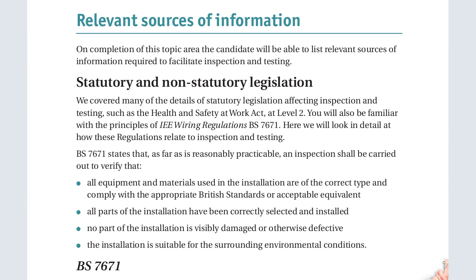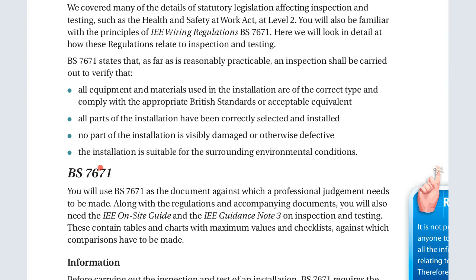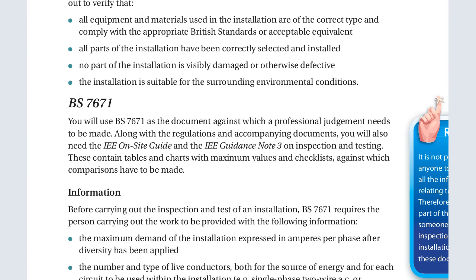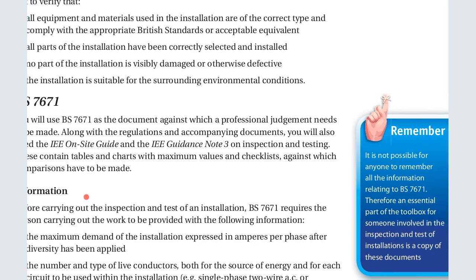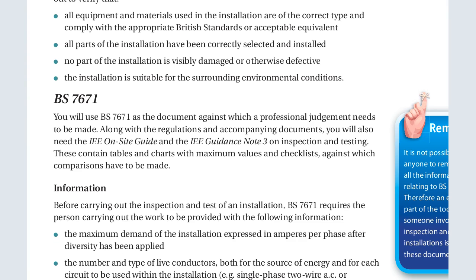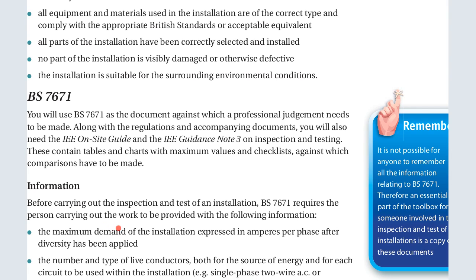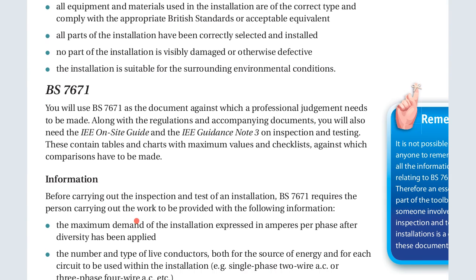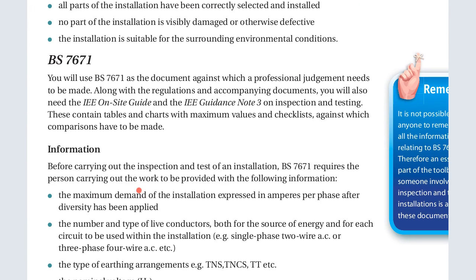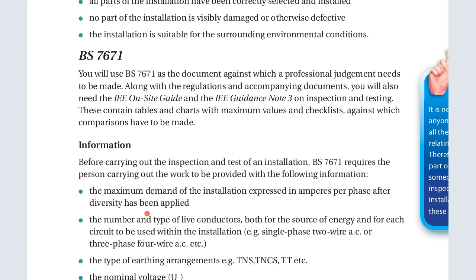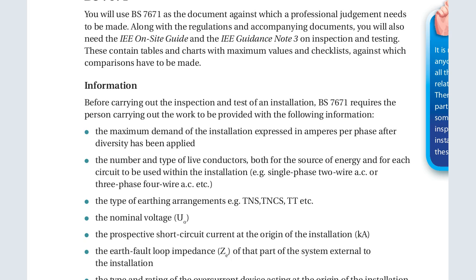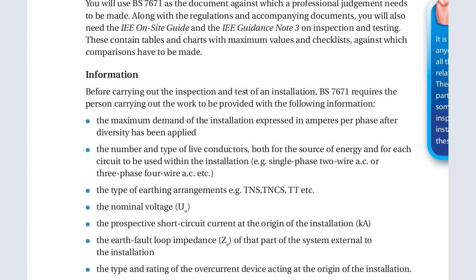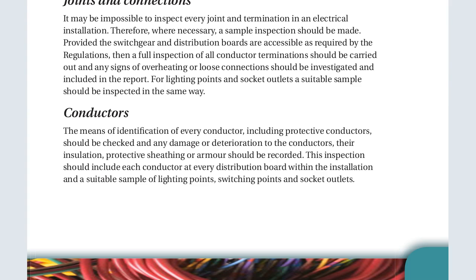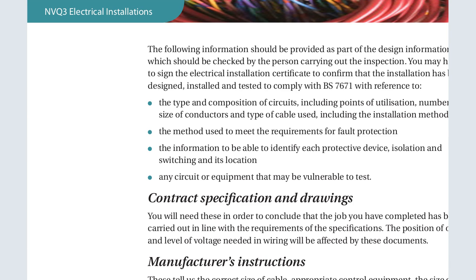Relevant sources of information, that is the statutory and non-statutory regulations. These are the IEE standards. Now, BS 7671, you will use this standard as the document against which the professional judgment needed is to be made, alongside the regulations and accompanying documents. You will also need the IEE On-Site Guide, that is the IEE guidance notes on inspection and testing. These contain the tables and charts, and information like the earthing, the nominal voltage, and all those things that are needed when you are doing the checking, the inspection, and testing.